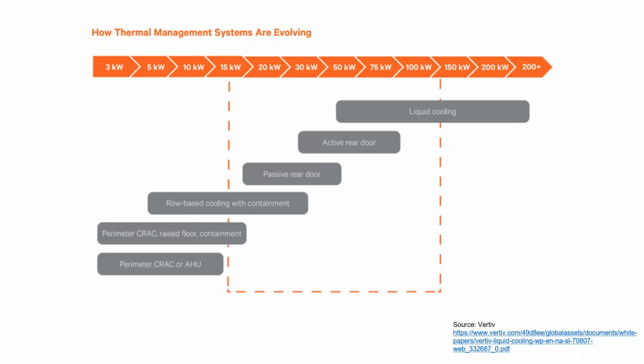When we look at the types of technology that can do this cooling, we see things like perimeter CRAC and CRAH units, raised floor and containment. We're at 15 kilowatts per rack and under. Then we get to row-based cooling with containment, so that's your hot aisle, cold aisle. You can do some good work there, but we're still in that 25 to 30 kilowatt range. That's basically the physical limits of air cooling. Then you get into hybrid things like rear door heat exchangers, and then we're into true liquid cooling at 50 kilowatts and up.